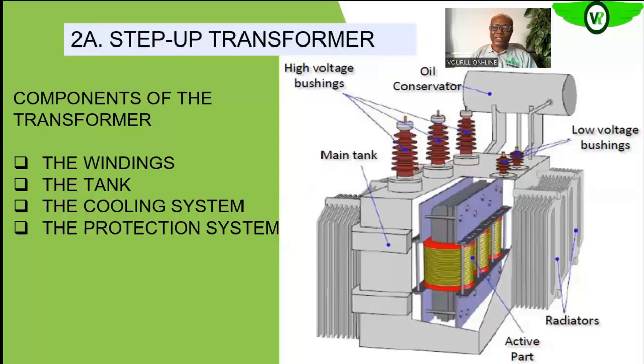Then we also have protection systems that protect the transformer against overload that will eventually cause overheating, and also against shortage of cooling oil, or shortage of transformer oil. Short to ground also, there are systems that protect the transformer against that kind of fault problem, over voltage, under voltage, and also internal faults within the windings. We have protection systems that protect the transformer against all of such. So we'll see some of them later in the course of this section of our training.